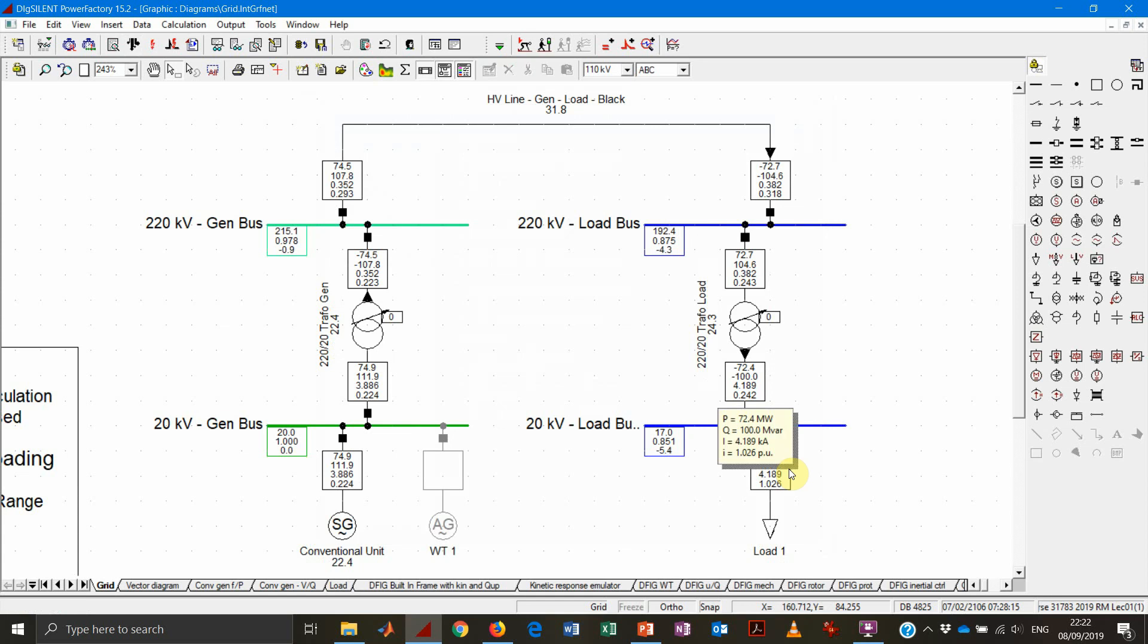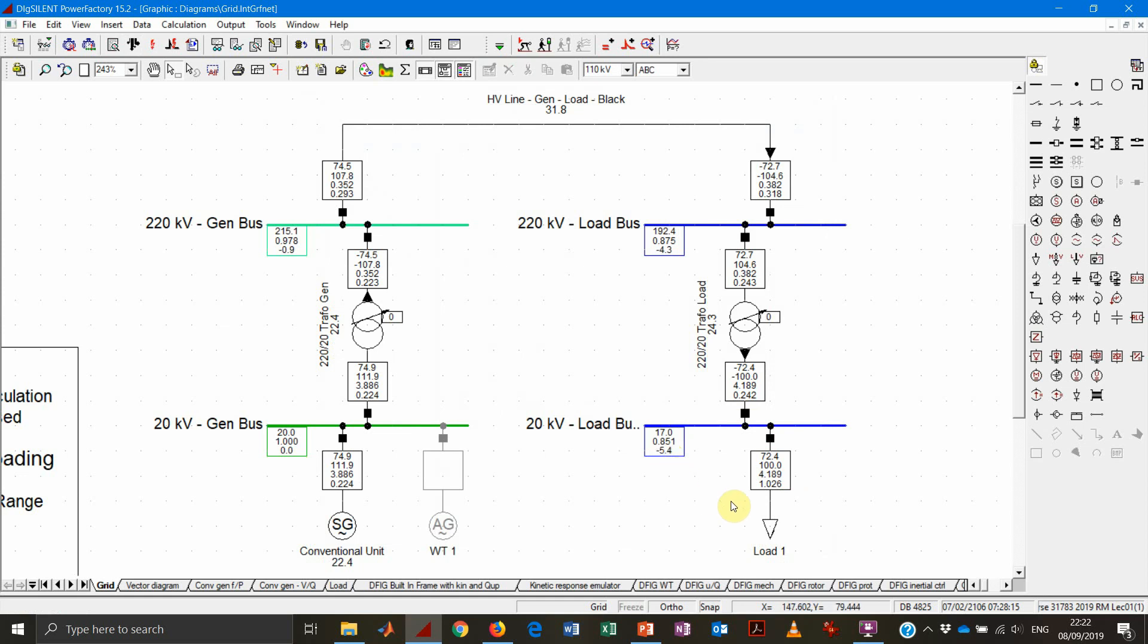You see now that we have a quadratic dependency for the active power, which pulled down to 72.4 megawatt, while the reactive power consumption is without any voltage dependency, so it's 100 megavolt-amperes reactive. You can also appreciate how the voltage got quite low, 85%, and also how important it is to correctly model the reactive power dependency on the voltage.